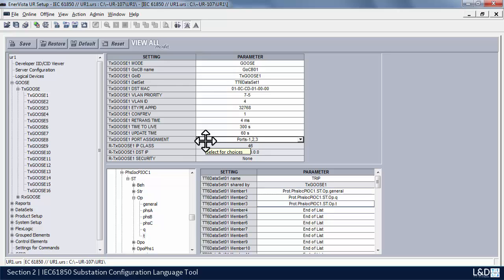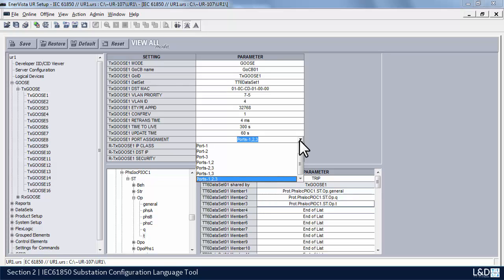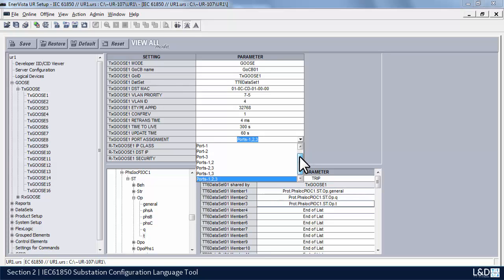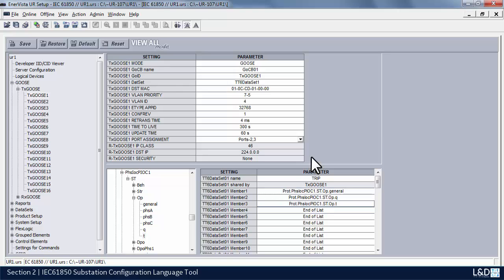The next field is port assignment. As a means of security, this setting specifies the Ethernet ports for transmitting the GOOSE message. We can pick and choose which port to transmit over — port 1, 2, 3, or any combination. We can also disable ports for security purposes. If you're using PRP or any form of redundancy, you'll need to set this to port 2 and port 3. If you look at the CID file, there would be no separate port 3 configuration — port 3 would have all the same elements as port 2: the same MAC address, IP address, and masking.